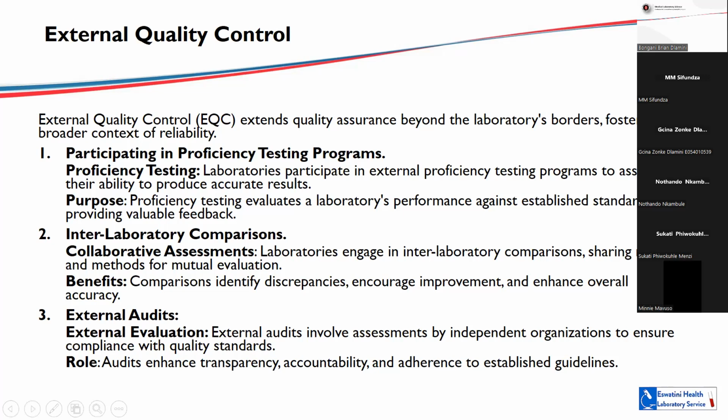And what is important with the EQA is whenever we receive these samples in our various laboratories, we need to treat them in a similar manner to how we treat our routine patient samples. So they don't need special treatment or special care, because they are aimed at testing the overall system, from the pre-analytical and analytical to the post-analytical, to see if everything is done accordingly.